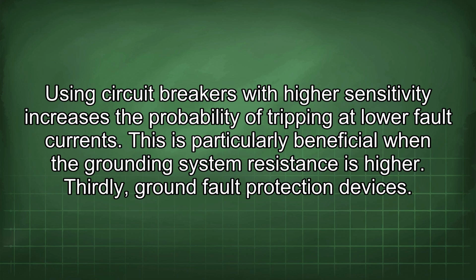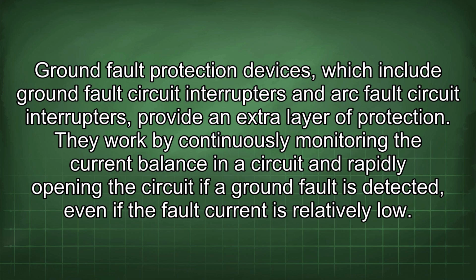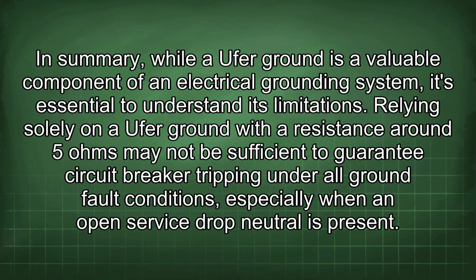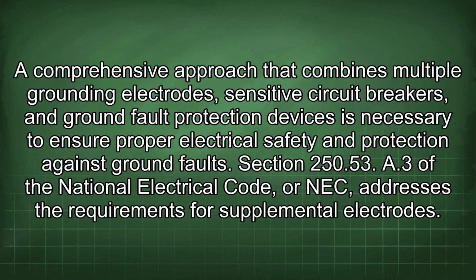Thirdly, ground fault protection devices. Ground fault protection devices, which include ground fault circuit interrupters and arc fault circuit interrupters, provide an extra layer of protection. They work by continuously monitoring the current balance in a circuit and rapidly opening the circuit if a ground fault is detected, even if the fault current is relatively low. In summary, while a Ufer ground is a valuable component of an electrical grounding system, it's essential to understand its limitations. Relying solely on a Ufer ground with a resistance around 5 ohms may not be sufficient to guarantee circuit breaker tripping under all ground fault conditions, especially when an open service drop neutral is present. A comprehensive approach that combines multiple grounding electrodes, sensitive circuit breakers, and ground fault protection devices is necessary to ensure proper electrical safety and protection against ground faults.